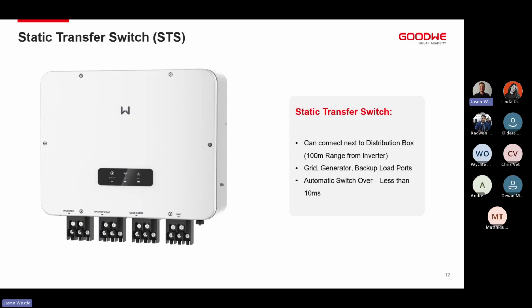If we get into year 12 or year 13 on the project, it is a lot cheaper or a lot more cost effective to replace a section of the inverter, being the STS, as opposed to replacing the entire inverter itself. So by having it separate, 1, we are able to save money outside of warranty if we need to replace. And then secondly, and this is where it becomes the most vital or the biggest point with regards to why the STS is separate, is the fact that we can install this up to 100 meters away from our DC connection, or from 100 meters away from our inverter.